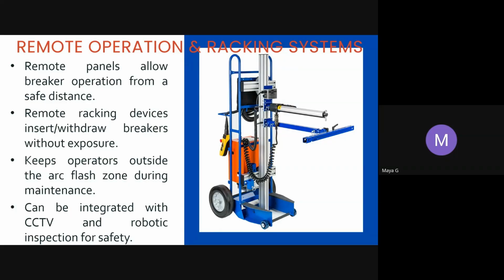Remote operation and racking system. Remote panels allow breaker operation from a safe distance. Remote racking devices, as shown in the figure, will insert or withdraw breakers without exposure of the worker to the high voltage or medium voltage system. This keeps the operator outside the arc flash zone during maintenance. It can also be operated by integrating CCTV and robotic inspection for safety purposes.